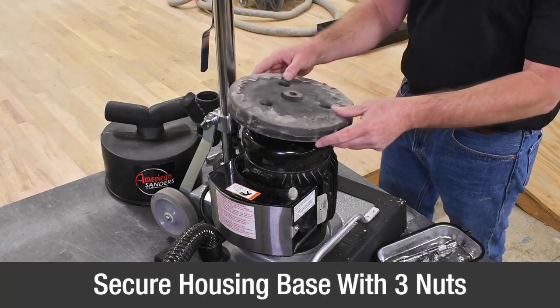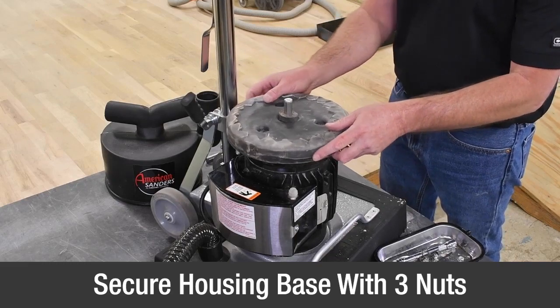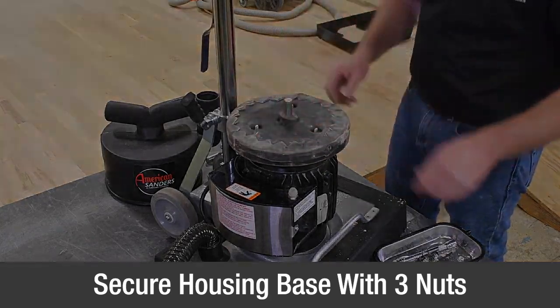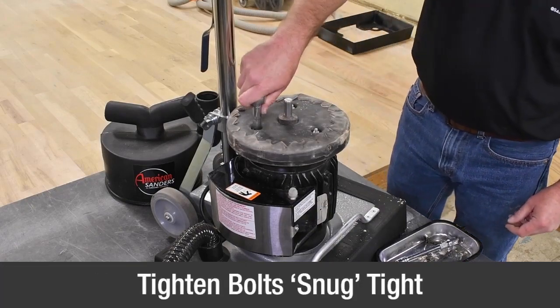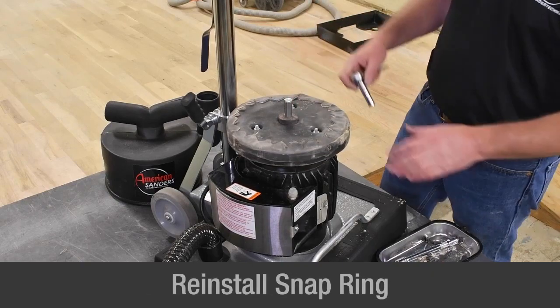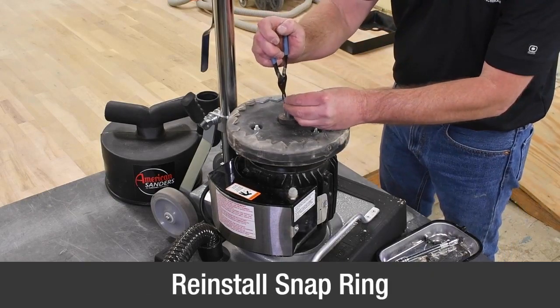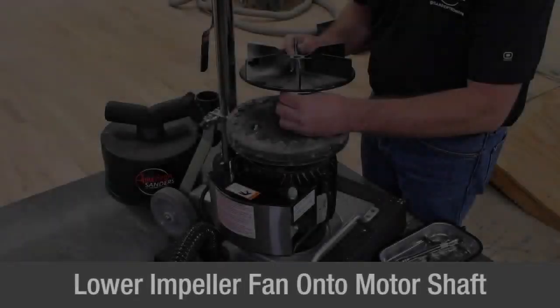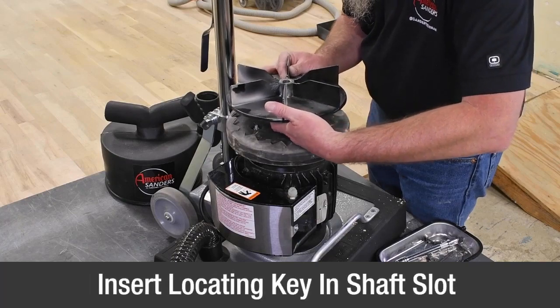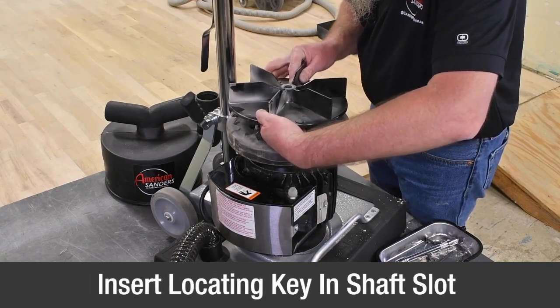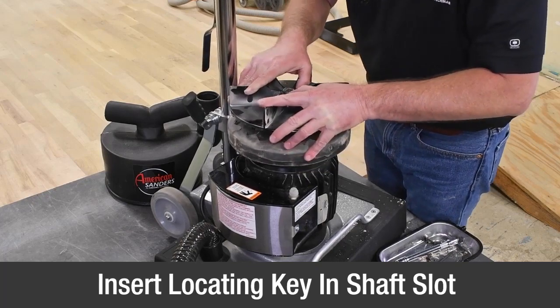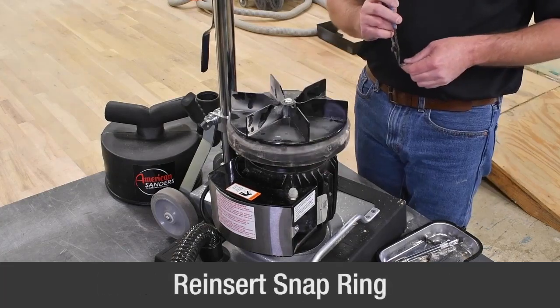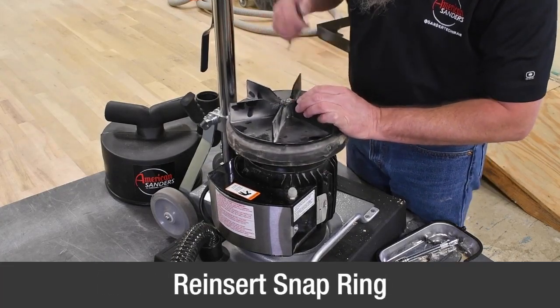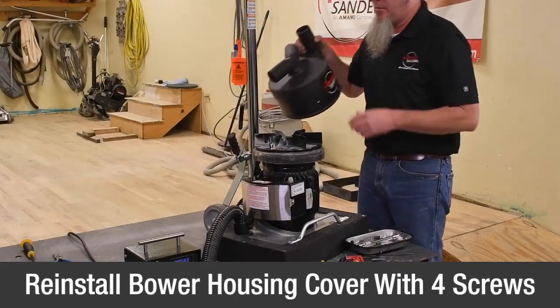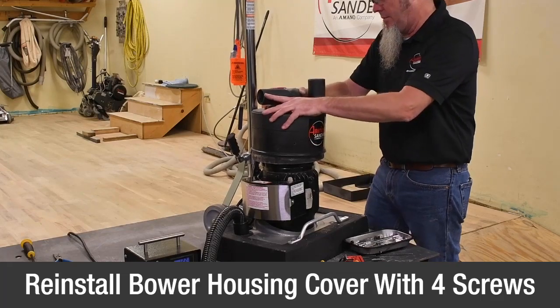Reinstall the housing base by lowering it onto the shaft and secure it with the 3 nuts. The 3 nuts should be snug, do not over-tighten. Reinstall the snap ring on the shaft. Reinstall the impeller. Be sure to put the locating key in the shaft slot. Then reinstall the upper snap ring on the shaft to keep the components secure. Position the new blower housing cover onto the housing base and reinstall the 4 screws securely.